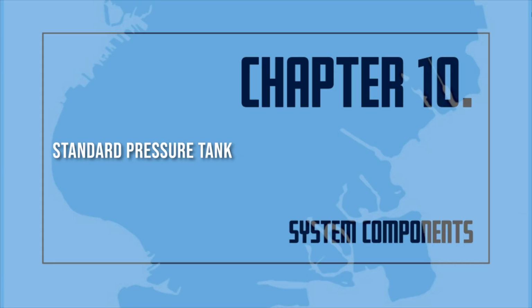Standard pressure tank. Pressure tank alarms. All pressure tanks used to provide the required primary water supply for a sprinkler system shall be equipped with 2 high and low alarm systems. One system monitors the high and low air pressure. The other system monitors the high and low water levels. The alarm system automatically monitors the air-to-water volume ratio, which should always be 1 air to 2 water. An alarm signals the certificate of fitness holder or central station operator when the water level or the air pressure falls too high or too low. When this occurs, the pressure tanks should be adjusted or repaired immediately.